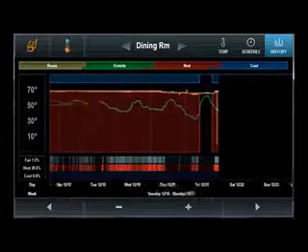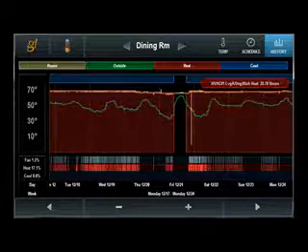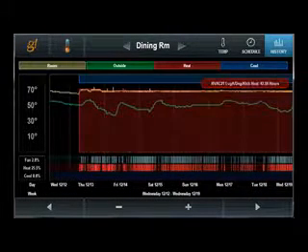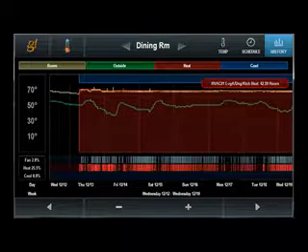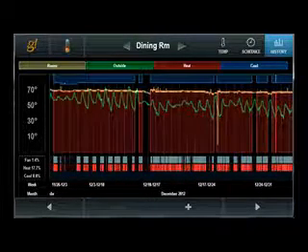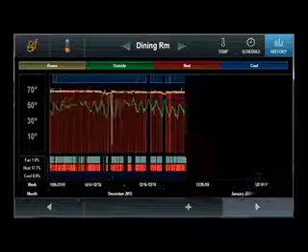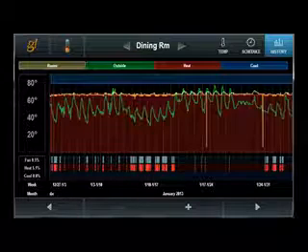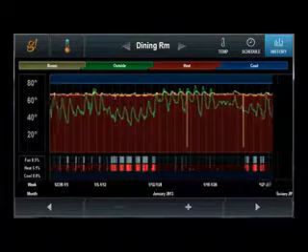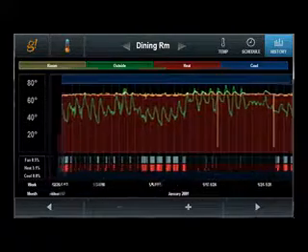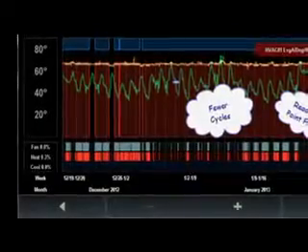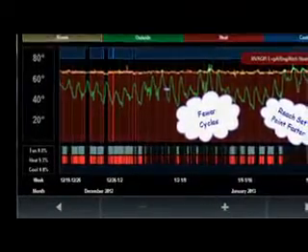So the air that was being expelled through the supply registers, instead of being pointed and directed down to the living space where the temperature sensor was, was being sent directly to the vaulted ceiling, where it settled as heat rises, and the lower temperature sensor never reached temperature because the heat wasn't getting down. So he flipped the registers around and made an adjustment to the set point, and you can see now these had much lower use of that HVAC and saved a lot of money.